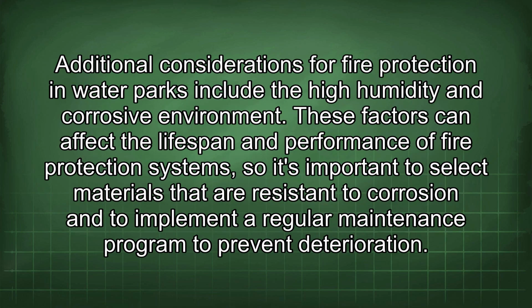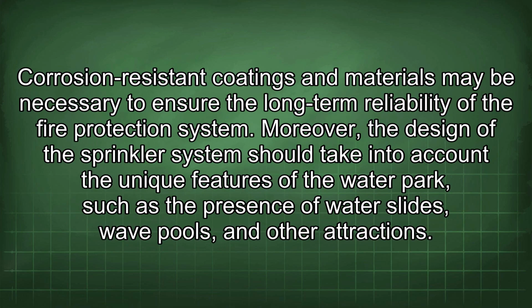Additional considerations for fire protection in water parks include the high humidity and corrosive environment. These factors can affect the lifespan and performance of fire protection systems, so it's important to select materials that are resistant to corrosion and to implement a regular maintenance program to prevent deterioration. Corrosion-resistant coatings and materials may be necessary to ensure the long-term reliability of the fire protection system.